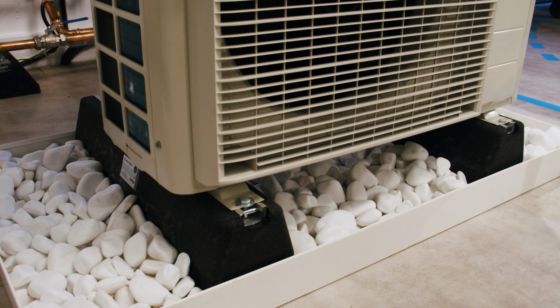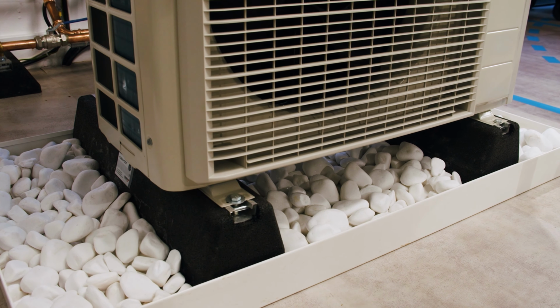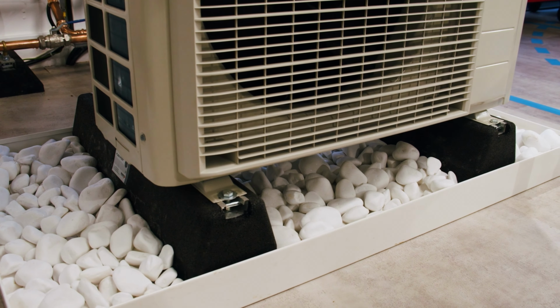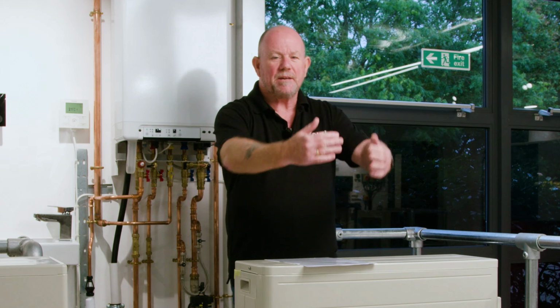The unit will need to be so far away from a wall. We'll need to have clearance to its left and clearance to its right. And most importantly of all, we'll need to have clearance in front of it. If you think about the air, we're taking the air onto the unit, we're extracting energy from the air, and then we're discharging that air.